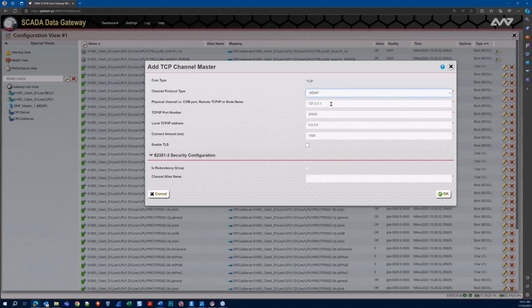Then I need to give it the IP address of the outstation I want to connect to. In this case, I know that this will be 10.10.10.153, and my port number is going to be 20001. My local IP I can leave at default right now. If I have multiple IPs on my machine, I could choose one to bind to for my outgoing connection, but for right now I can just leave that at the default.